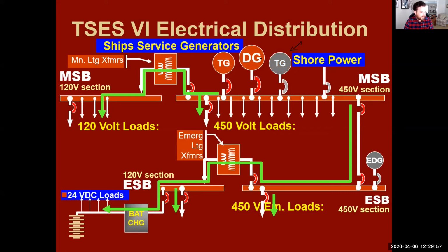And if that happens, and we can't get load to be picked up, we might possibly lose both TGs. Our diesel generator will come on a few seconds later, I believe around 20 seconds. But the next thing that happens is the diesel generator breaker will close and try to power the main bus. If there's a problem, if these three can't handle it, something unexpected happens, that's why it's called an emergency, and we lose power to all three of those. They are not providing power to our main switchboard.